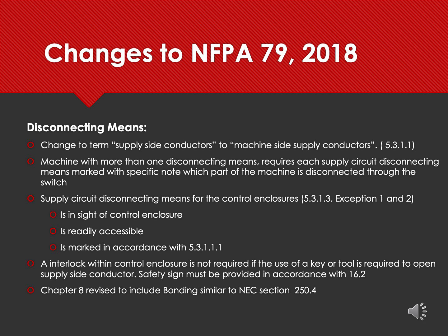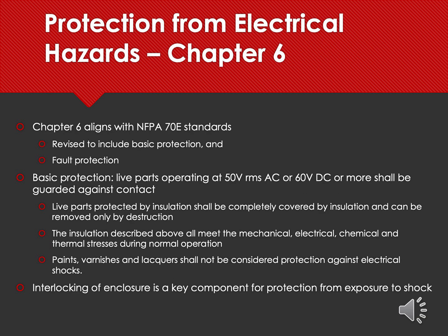Let's go to the next slide. So in this slide we talk about electrical safety, which is totally in our wheelhouse here at Grace Engineered Products. This section again aligns directly with NFPA 70E standards for workplace electrical safety. So here are the changes. Language to warn against electrical hazards was removed from NFPA 79, and this section uses some new terms for basic protection and fault protection definitions.